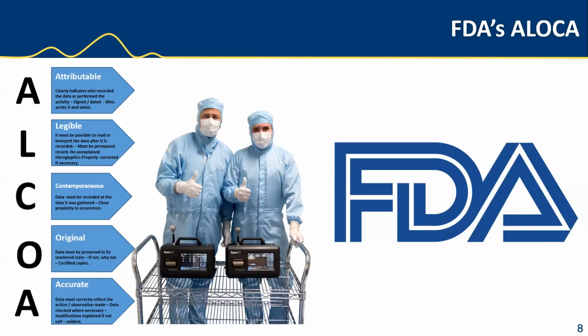O stands for original. Source data or raw data is what's meant by original data. It's the first data and therefore considered the most accurate and reliable. It doesn't matter if the data has resulted in a pass or fail. It should be preserved in its original unaltered state or recorded as a true certified copy for reference purposes. Auditors must be able to trace metadata, the calculations, the reports, and analysis results from the raw data directly to the source data.